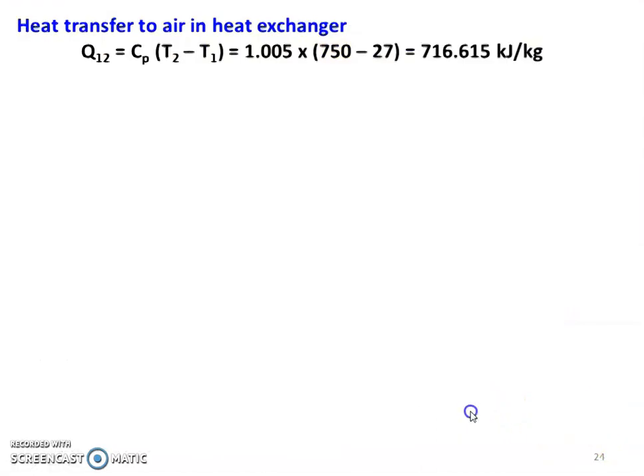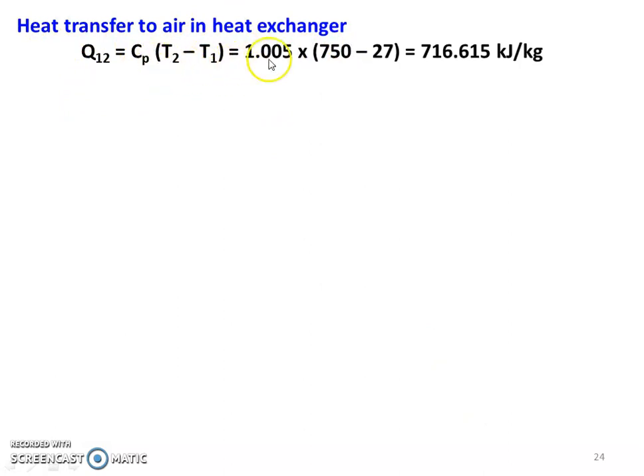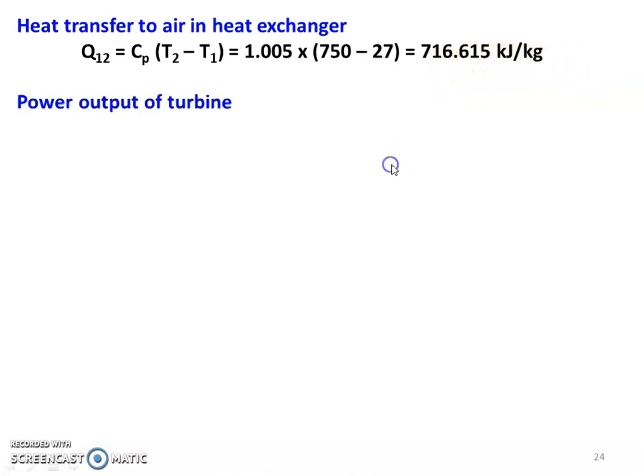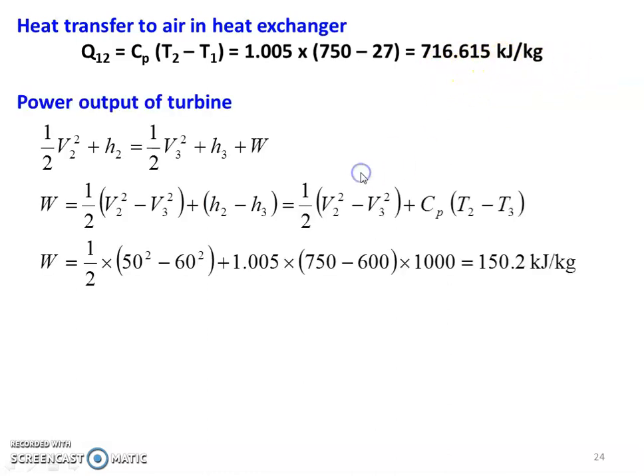First, the heat transfer to the air in the heat exchanger: Q12 = CP × (T2 − T1) = 1.005 × (750 − 27) = 716.615 kJ per kilogram. Then we find the power output of the turbine.